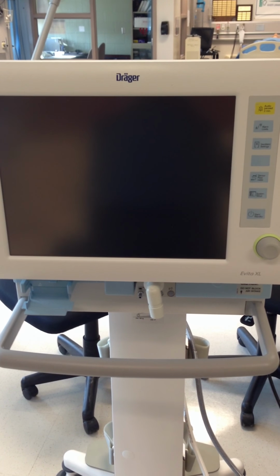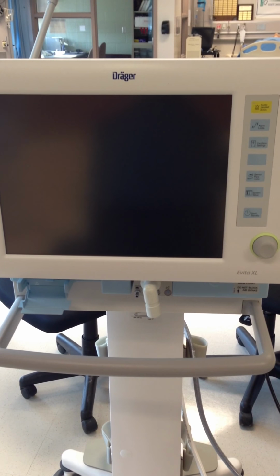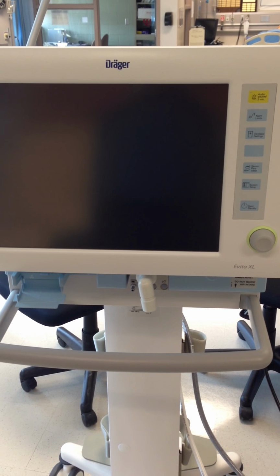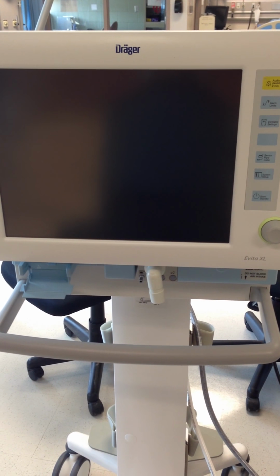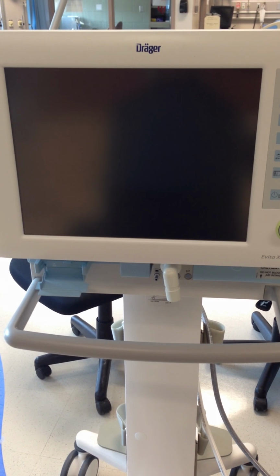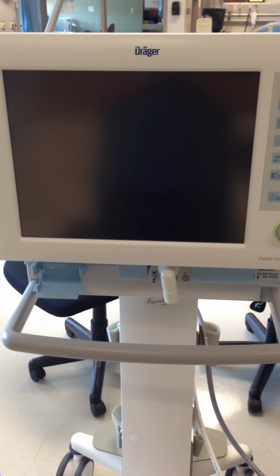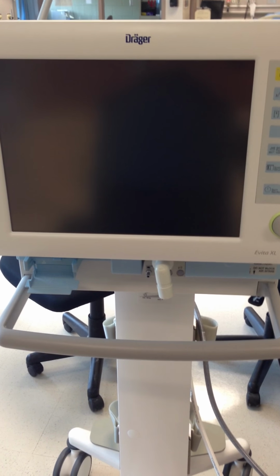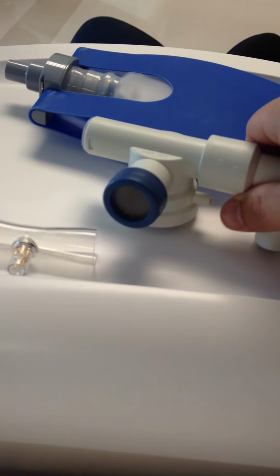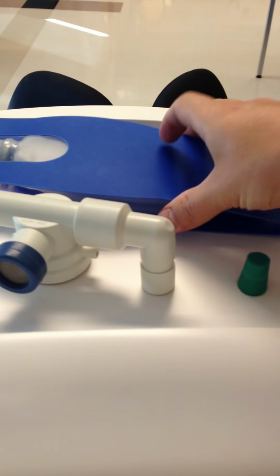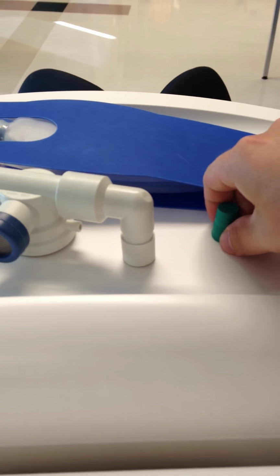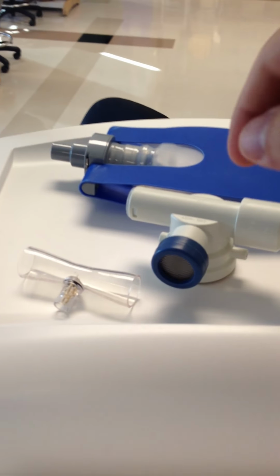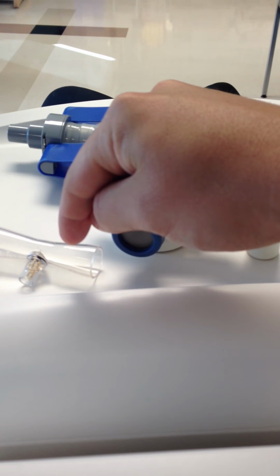Okay, so this is the Draeger Evita XL, another very user-friendly ventilator from Draeger. And what we're going to do now is just do a short self-test, so an SST, to make sure the device is functioning properly, and a leak test on the circuit. Things you're going to need for this are an expiratory valve assembly, a flow sensor, test lung, and something to plug the circuit with.